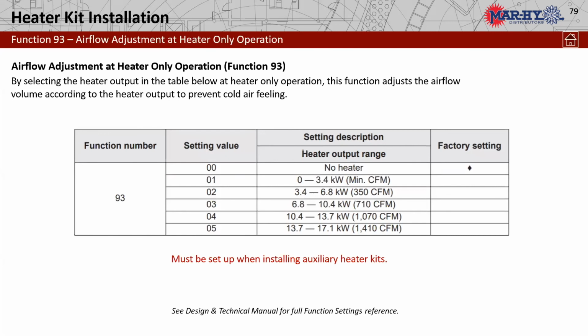Here is that airflow adjustment for function 93. Now, as you look at this, look at the CFMs. See what CFM fits that air handler to fit that kW package. For instance, I have a 2-ton here at the training center. I have it basically set up for 10 kW strip heat. Well, we want to use function 3, seeing that our CFM minimum is 710. That will suit a 2-ton unit. If you look at 04, that has a CFM minimum of 1070. Can't do that with a 2-ton.